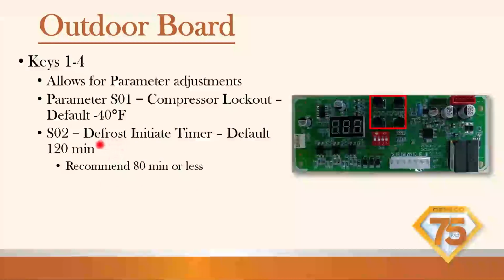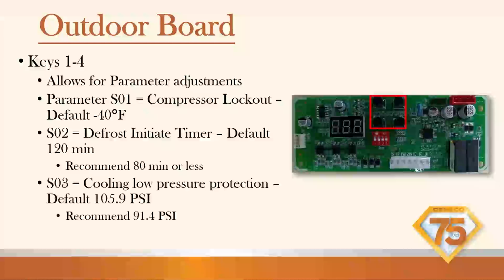Defrost initiate timer defaults to 120 minutes. So we do want you to change that to 80 minutes or less, because at 120 it'll allow the unit to run all iced up for 2 hours. At 80 minutes or less, it'll go into defrost more frequently if needed. And compressor lockout defaults to -40. So leave that, because we want that compressor to keep running as long as it can.